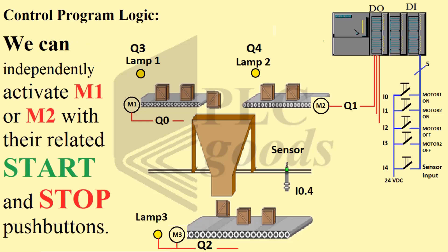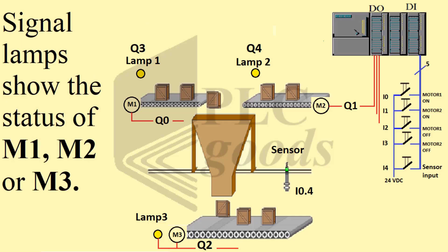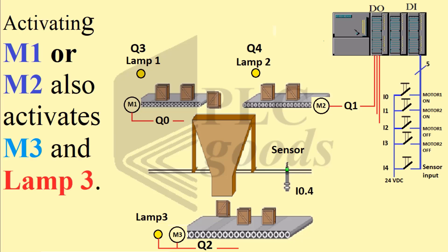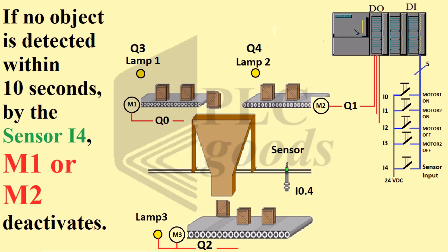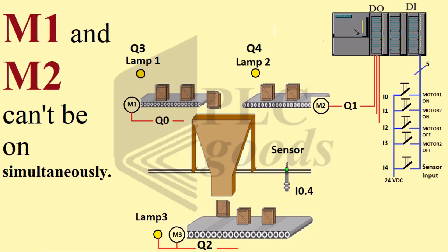The control program logic allows us to independently activate M1 or M2 with their related start and stop push buttons. Signal lamps show the status of M1, M2, or M3. Activating M1 or M2 also activates M3. After pressing any related stop push button, M1 or M2 stops after five seconds and M3 after seven seconds. If no object is detected within 10 seconds by sensor I4, M1 or M2 deactivates. M1 and M2 cannot be on simultaneously.